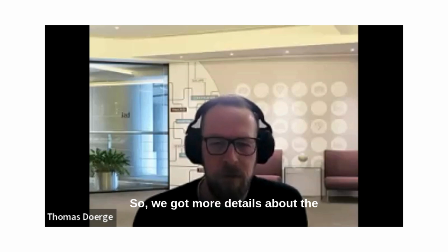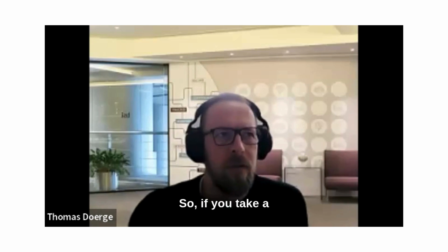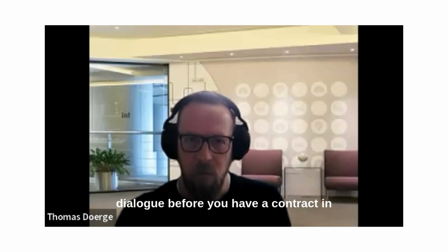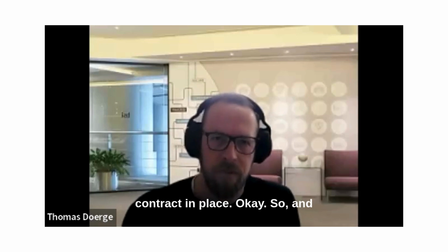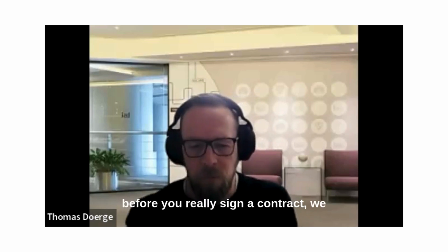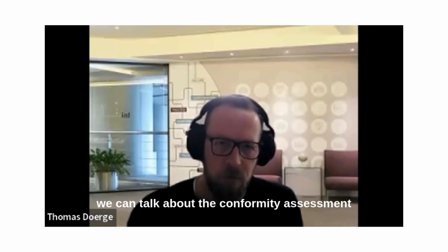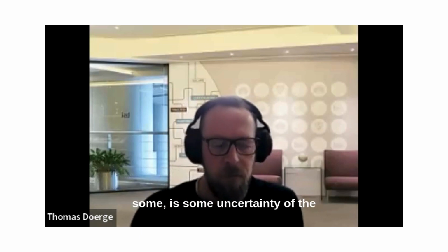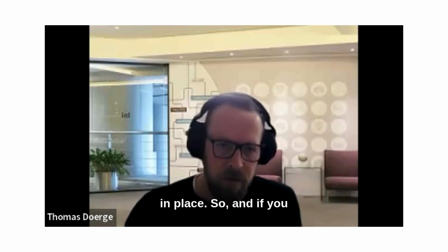We have more details about the structured dialogue in MDCG 2019-6 revision 5. If you take a look at that document, you can see which topics can be covered in that dialogue before you have a contract in place with the notified body and after you have a contract in place. Before you really sign a contract, we can talk about general requirements. We can talk about the conformity assessment itself. So if there is some uncertainty about the requirements in the MDR in general, that can be covered before you have a contract in place.